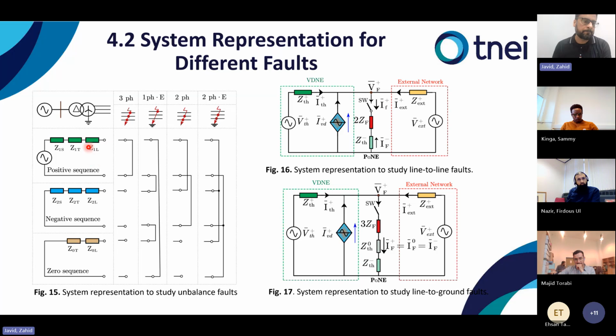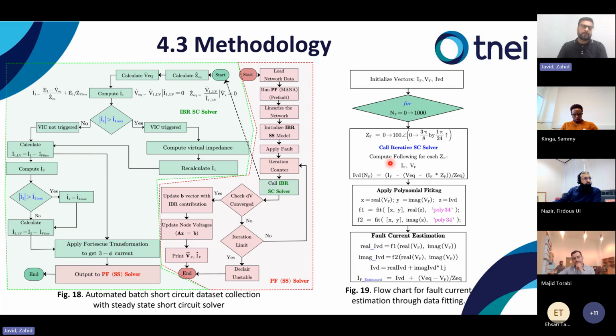For example, this is the system representation in the different sequences. In the negative sequence, we don't represent the source, we short circuit it, and in the zero sequence, we don't represent the source impedance as well. So according to these, we can modify the positive sequence voltage dependent network equivalent according to the fault. And this was the main methodology that we used to gather that data, and then after gathering the data set, how we can parameterize the figure 18.